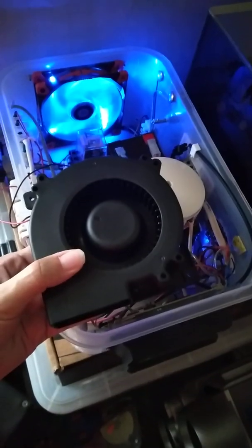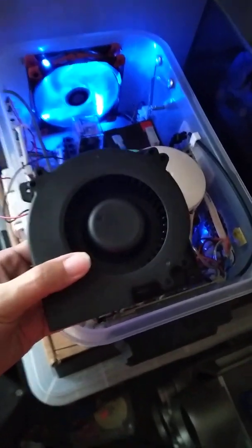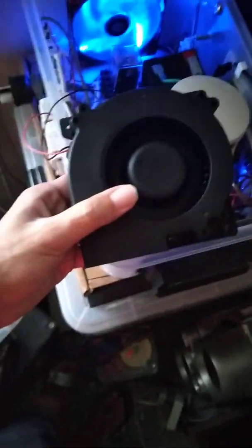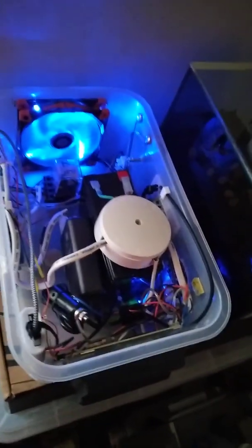So the additional power that a blower consumes is actually what it needs to generate the additional pressure required to force air through things such as filters. I'm not referring to mesh filters though, but more substantial filters like cloth or HEPA filters and carbon filters. So that actually sums it up pretty much. Everything serves a purpose, and you just need to choose the right fan for your application.